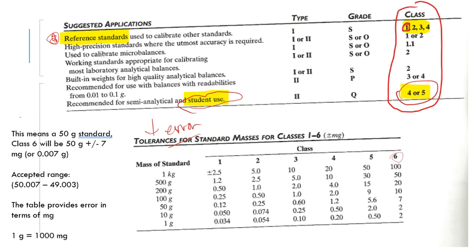So for instance, let's say that I take a 50-gram calibration standard. So here's the 50-gram calibration standard, and there's class 1 and class 2 and class 3, class 4, class 5, and class 6. So what you're seeing with the tolerance, aka error, is that as we go up in the class, the calibration set gets worse and worse. And the tolerance is a plus or minus. So that means it could be over or it could be under. So my window gets bigger.